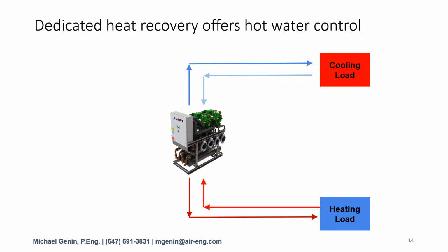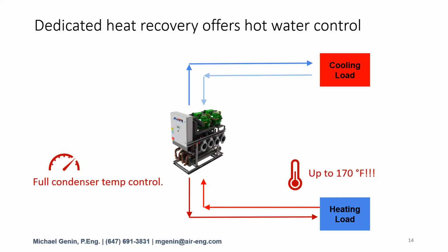The key takeaway is the chiller can watch both hot and chilled water sides, but it can only control to one of them. And it can only control to the lesser of these two loads. If the heating load is low, it will control to this, and it will not be able to keep up with the cooling load. If the cooling load is low, it will control to this and it won't keep up with the heating load. In most instances, you don't have a perfect simultaneous load, so additional measures are required.